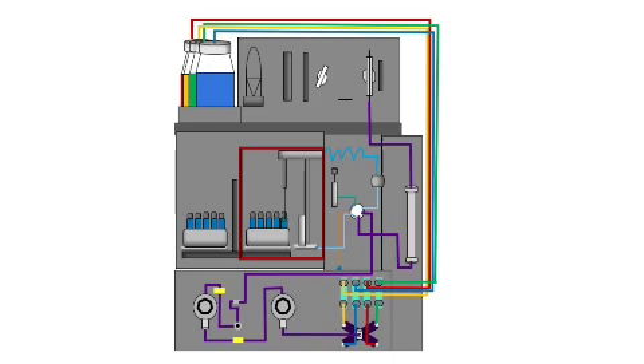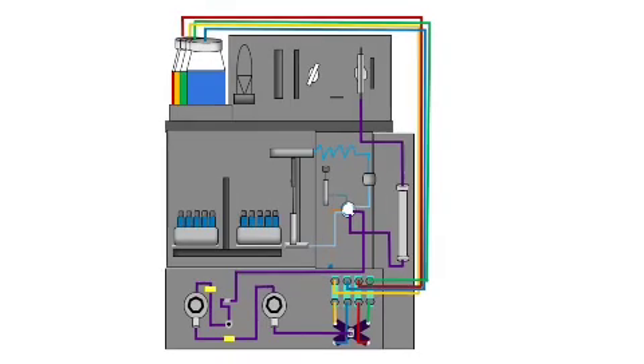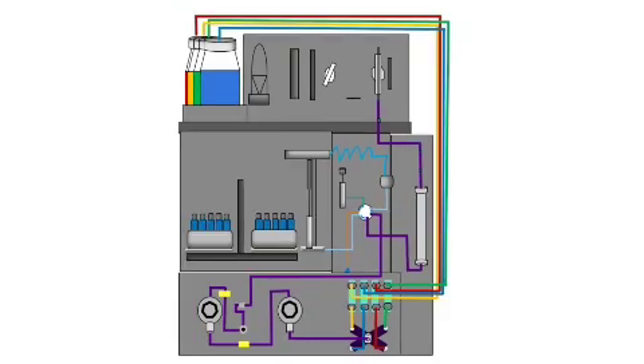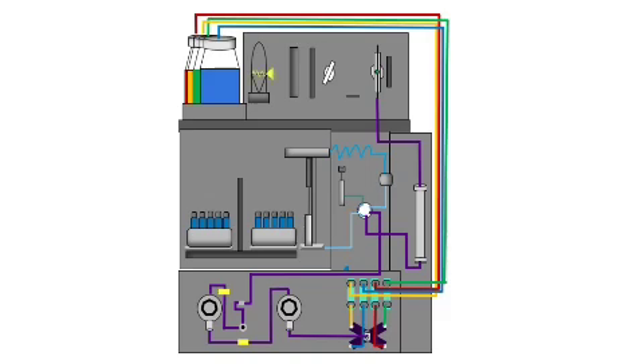When the sample is injected, it travels through the needle to the injection valve, then through the column where the mixture separation takes place. The separated analytes travel to the flow cell of the detector. The detector passes light through the flow cell, measures the absorbance, and processes the signal to produce a chromatogram.